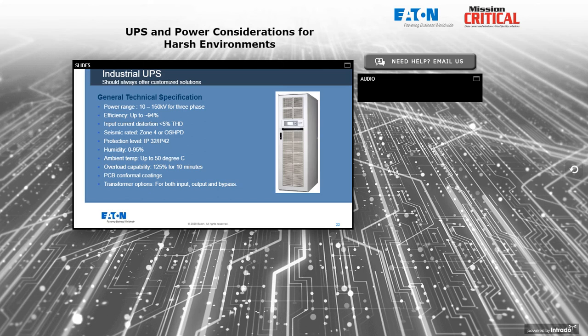Is it because the UPS needs the transformer to be rugged and work properly? Not necessarily. But if the client does require, for example, common mode noise isolation, a transformer-free UPS is generally not going to provide a very high level of common mode noise isolation. So a transformer needs to be placed in between the UPS and the critical load we're supporting. So whether that's put inside the case of the UPS or deployed separately, that's going to be the best way to improve common mode noise isolation, and that depends on what the critical load requires.